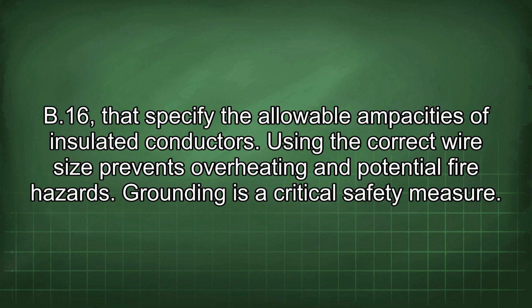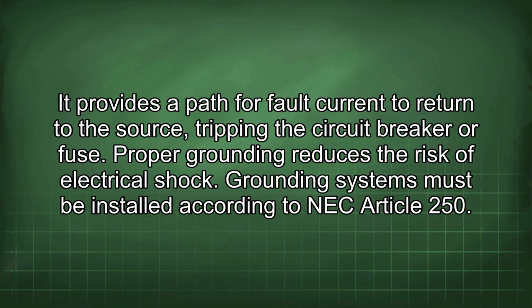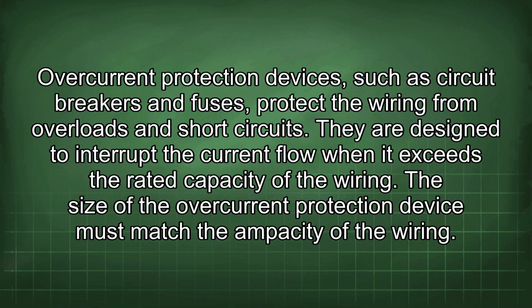Grounding is a critical safety measure. It provides a path for fault current to return to the source, tripping the circuit breaker or fuse. Proper grounding reduces the risk of electrical shock. Grounding systems must be installed according to NEC Article 250. Overcurrent protection devices, such as circuit breakers and fuses, protect the wiring from overloads and short circuits. They are designed to interrupt the current flow when it exceeds the rated capacity of the wiring. The size of the overcurrent protection device must match the ampacity of the wiring.